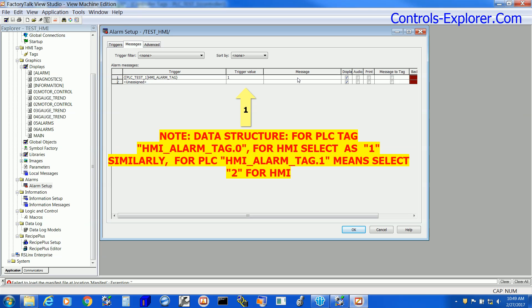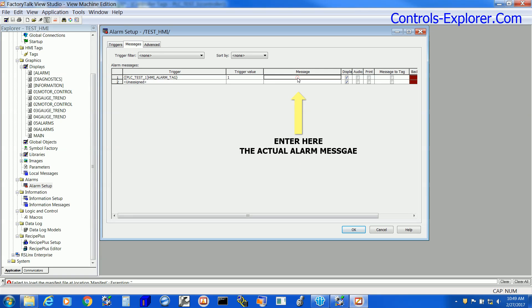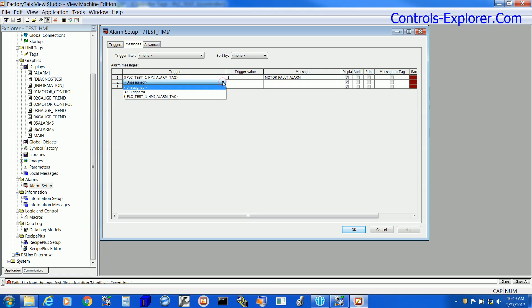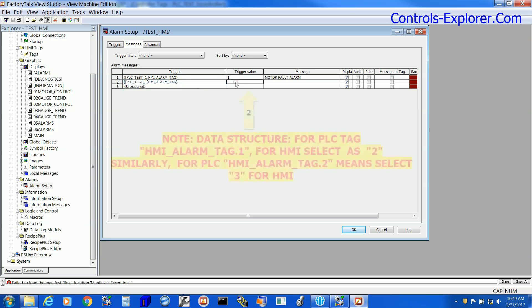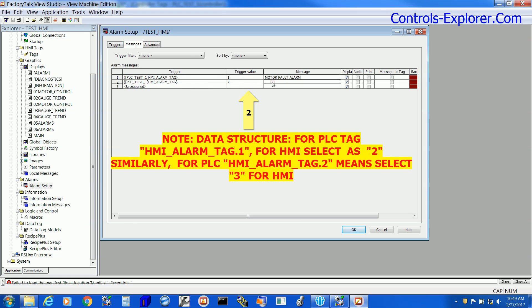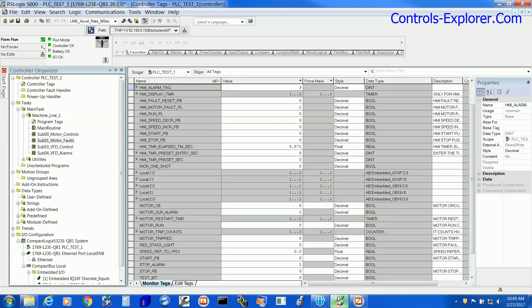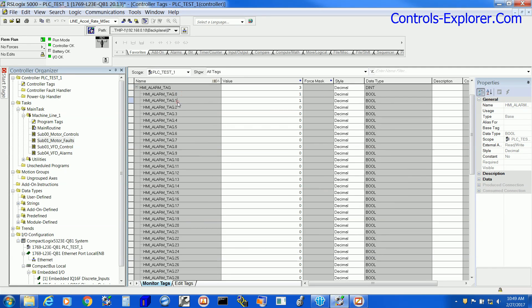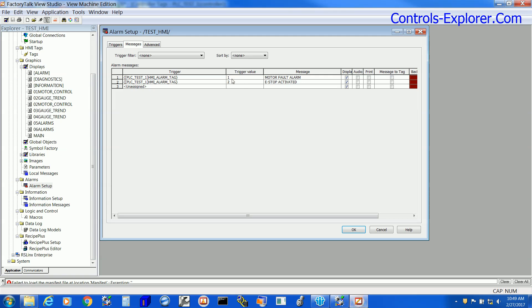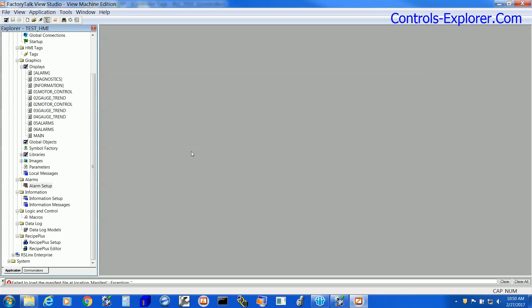So bit 0 in the PLC, which is 1 in the HMI, is the Motor Fault Alarm. The same thing applies: tag value 2 in the HMI corresponds to bit 1 in the PLC, which is the E-Stop Alarm. So the trigger values 1 and 2 in the HMI correspond to bits 0 and 1 in the PLC. We are done with this configuration — hit OK.